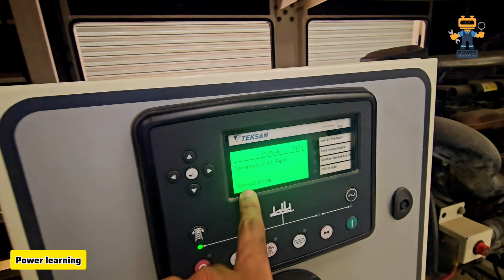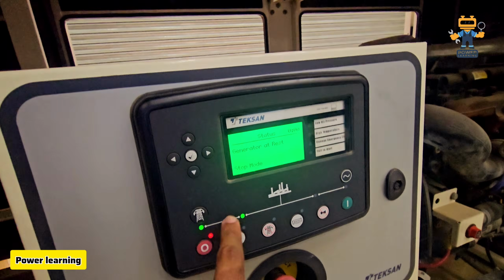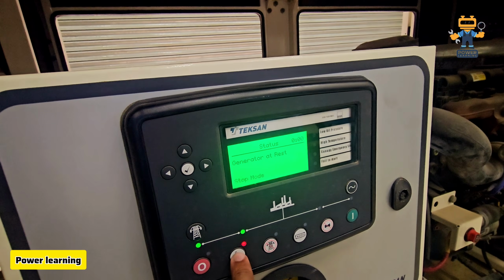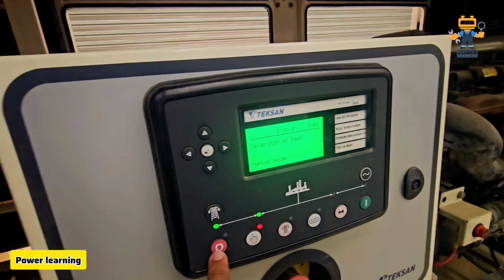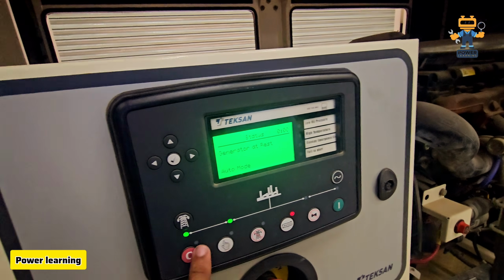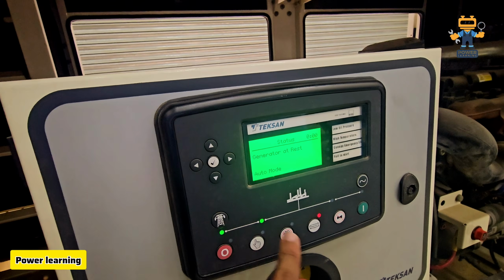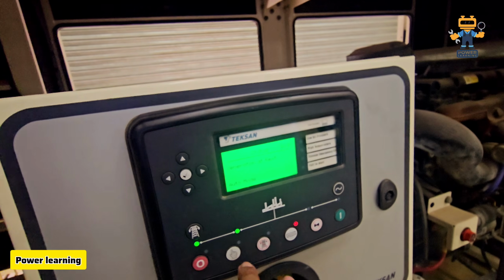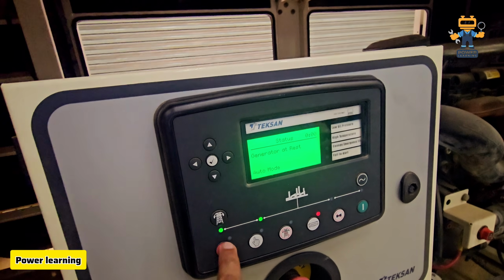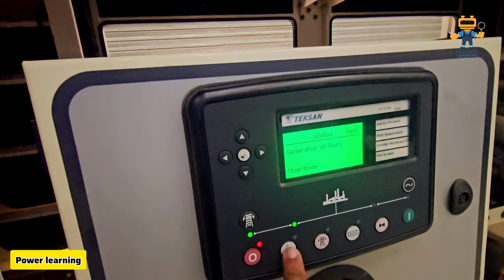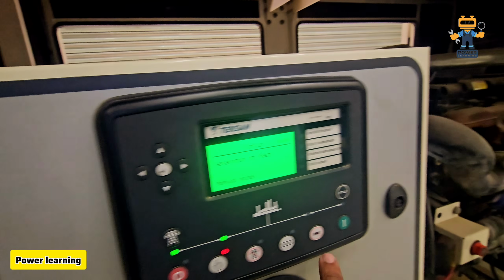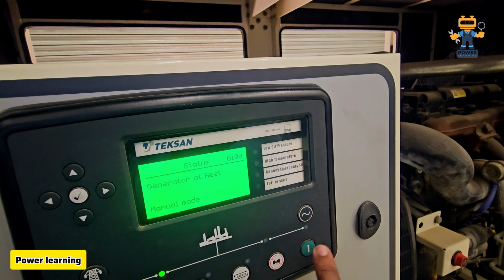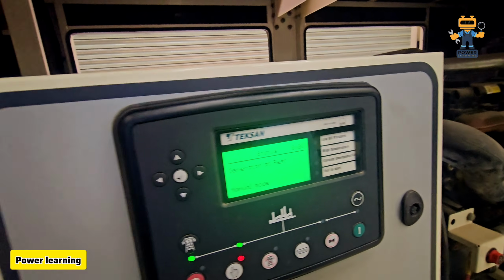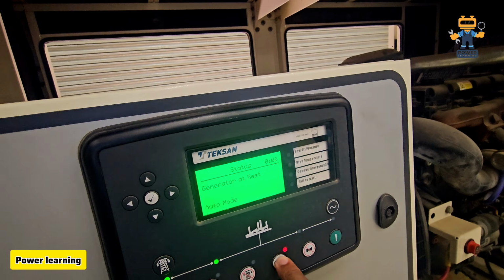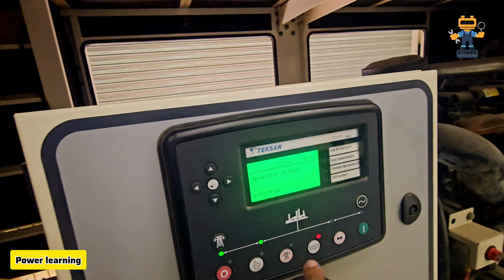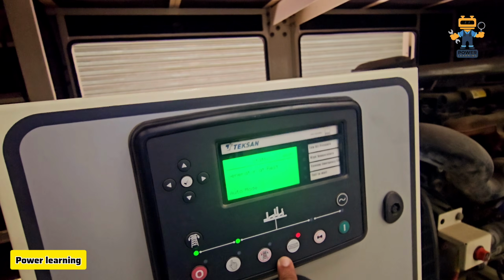So now manual mode is selected. Here, if you see, this is stop mode. Here, this is manual mode. And here we have auto mode. So these are the modes: auto mode, manual mode, stop mode. If we select manual mode, we have to press this green button to start the engine. But if we have auto mode, the signal must come from the ATS panel.